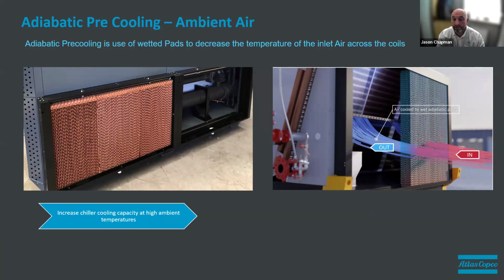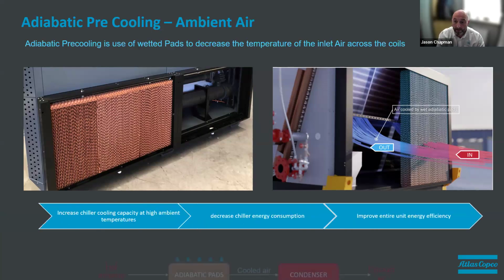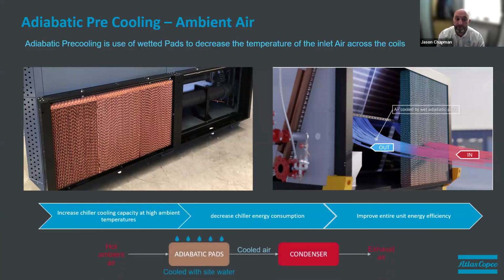The air passes over it. It's cooled as it goes through the adiabatic pads, and then it goes to the coolers. It decreases the chiller energy consumption, so they don't have to run as hard because you're already pre-cooling the air. It improves the entire unit efficiencies. And as we can see from the pictorial at the bottom there, once again, we've got the hot ambient temperatures coming in through the adiabatic pads, which are dampened and cooled, then over to the actual condenser and out through the bottom.